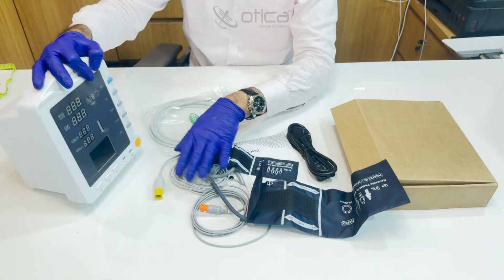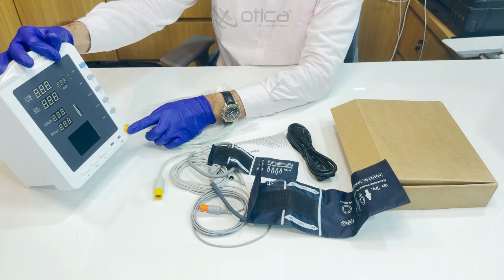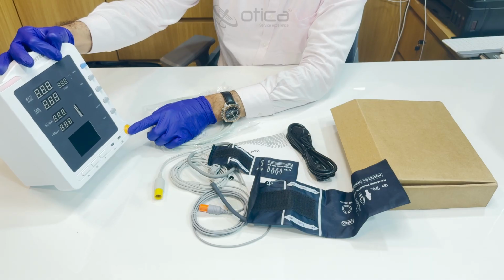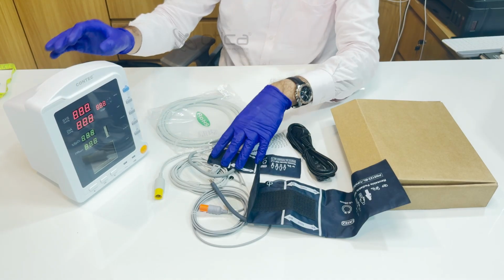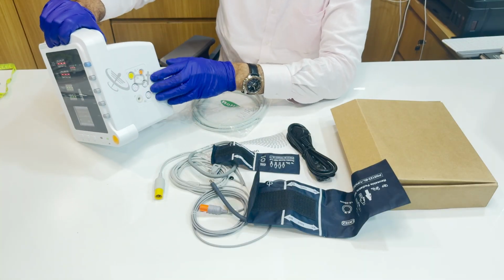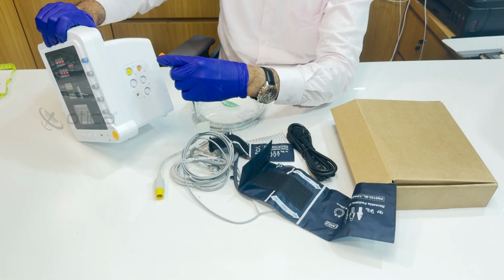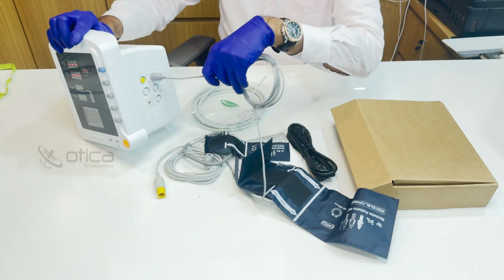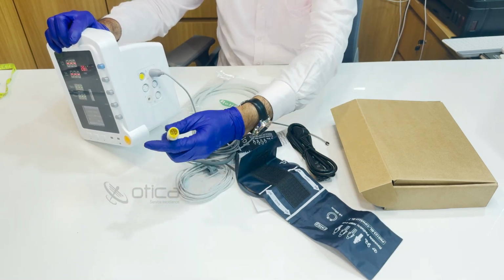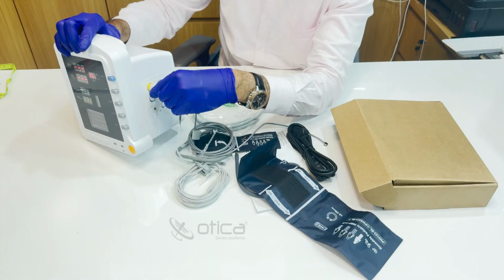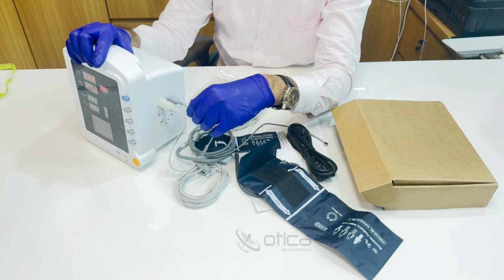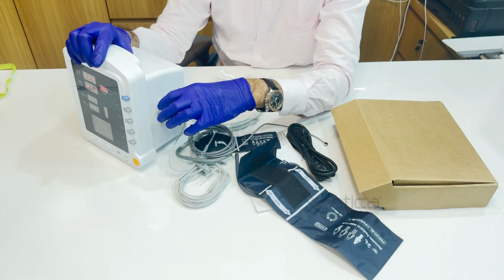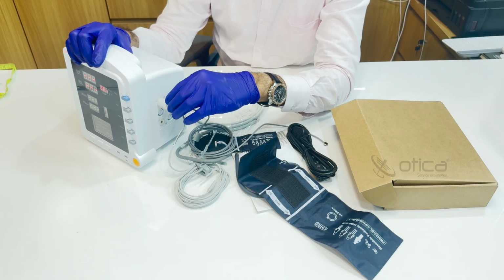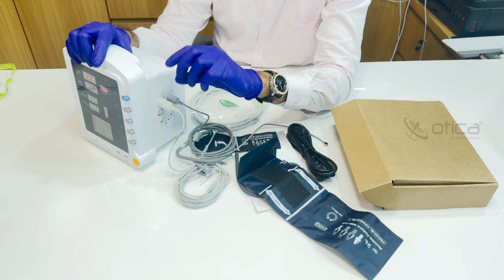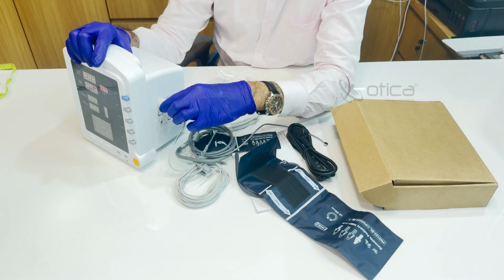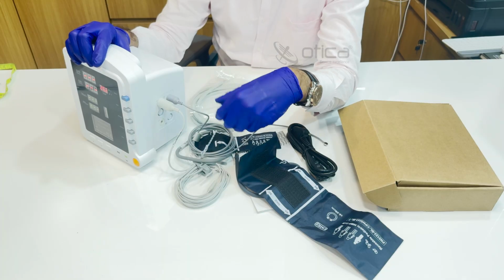Now we are going to switch on the device from the yellow button. You have to long press, so the device will switch on. There are the connection ports over here. You have to connect this orange port to the temperature probe. Then there is a yellow cord which is for the SpO2. You have to make sure you are using the proper connection for the proper cable, and do not rotate or twist the cable. You just need to pull and push.